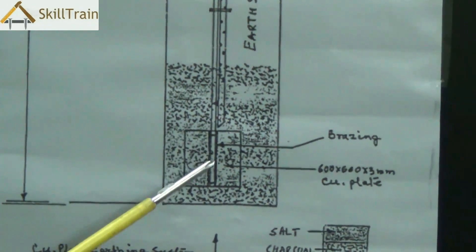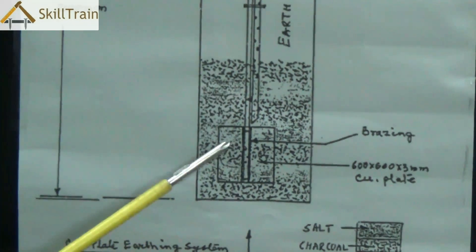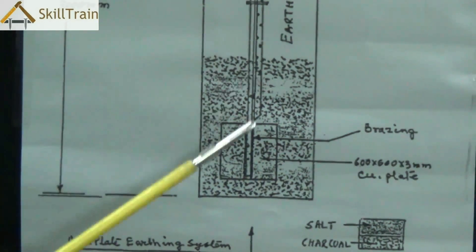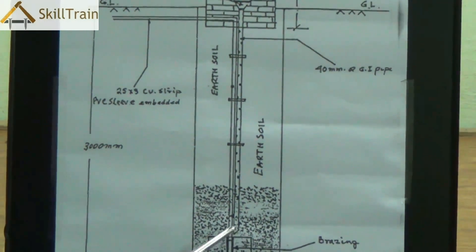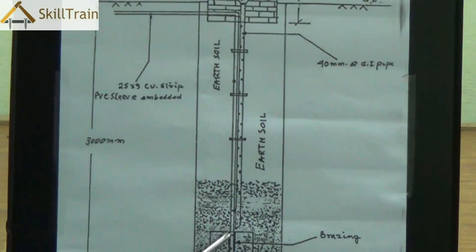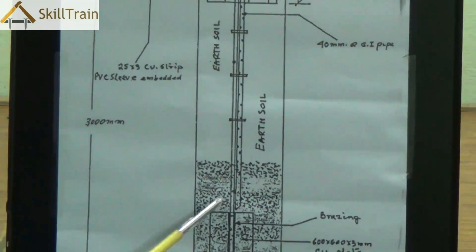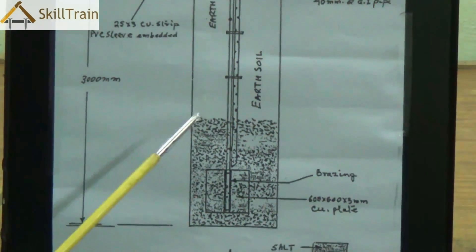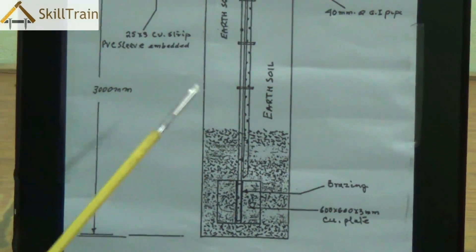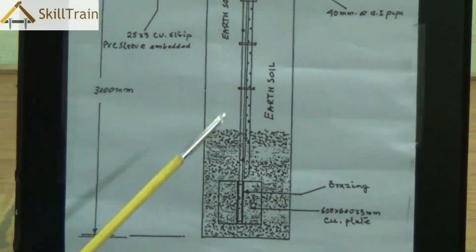A GI basically stands for galvanized iron plate. So we use a copper plate or a GI plate here underneath and this copper plate is then connected to a copper wire to the mains and then to individual plug points in each of the rooms. Now if you use a GI plate it's better to use a GI wire to connect it to the plug points or to the mains.